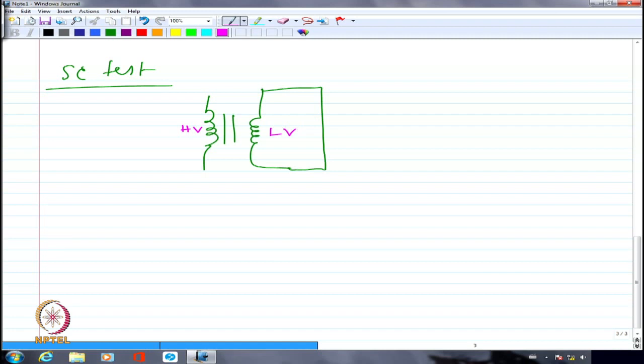The high voltage winding will have lower current, obviously. I want to pass rated current, right? 220 by 110 volts. We got 20 amperes as the current on the low voltage side. And on the high voltage side, it was only 10 ampere. So if I energize the high voltage side and have to pass rated current, then I don't have to worry so much because I don't have to look for a very high current source. So I would always try to energize the high voltage side when I am conducting the short circuit test.